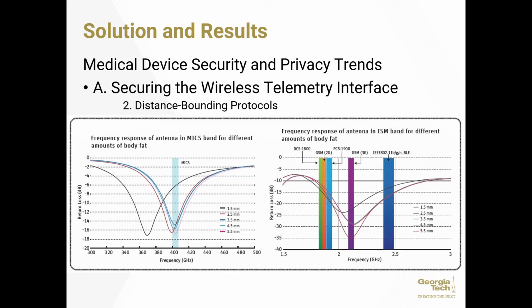Distance bounding is a technique that establishes physical distance between two entities by timing the delay of sent and received transmissions. This distance bound can be computed over various signals such as RF or ultrasonic sound. A number of IMD BAN access control and authentication protocols use distance bounding. However, distance bounding by itself provides for only weak authentication, in which physical proximity between the devices is established but identity and authorization are not, thereby requiring the use of additional authentication techniques. A typical distance bounding protocol between a programmer and IMD, for example, involves the programmer proving to the IMD that it is physically close, or within just 3 centimeters.